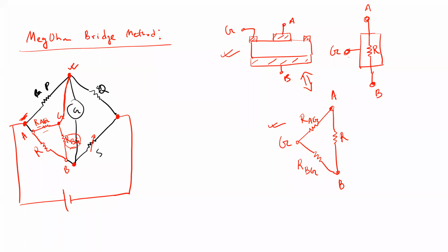On the other hand, your RAG is connected in parallel with P. Now, as we are dealing with insulation resistances, the insulation resistance and associated leakage resistances will be in the mega ohm range, suppose 100 mega ohms. And let us say P is 10 kilo ohms. Both of them are connected in parallel. So the equivalent resistance will be closer to which value? 100 mega ohms? 10 kilo ohms. It will be even lower than 10 kilo ohms actually. So in that case, we are eliminating the effect of this high resistance.